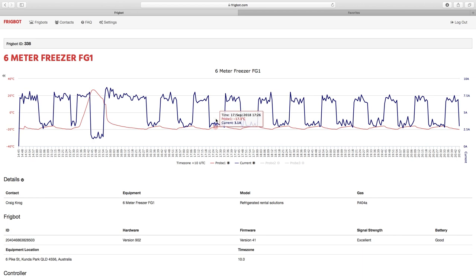Now why does it still draw current when it's reached its desired temperature set point? That's because the evaporator fans inside the room continue to run, the drain heater consumes power.